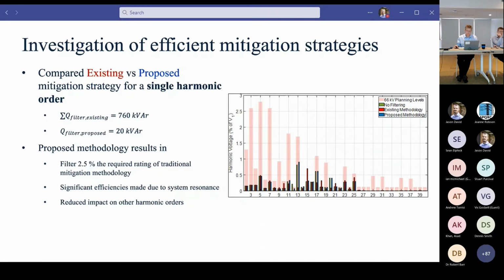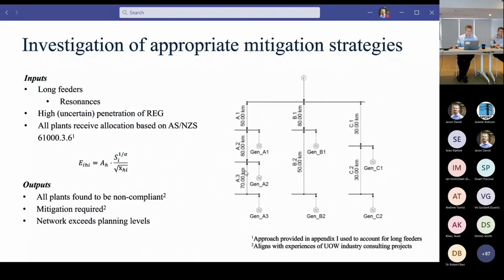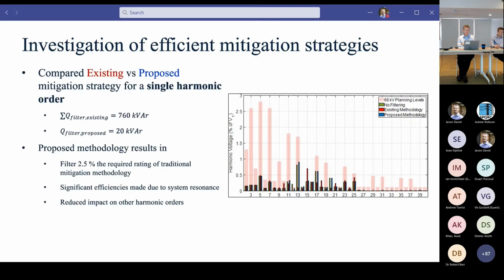So if we follow business as usual and connect a harmonic filter to the PCC of each of the generator connections, limiting the harmonic current that flows into the network and managing the harmonic voltage distortion within the network, what we find is that if we sum all of the ratings of the filters together, we've got about 760 kVAR of filtering spread out across the network itself. If instead, again, we go to the point of the network at which the planning levels are expected to be exceeded without any mitigation, the size of the filter bottoms out to about 20 kVAR. So this filter is about 2.5% of the business as usual methodology.